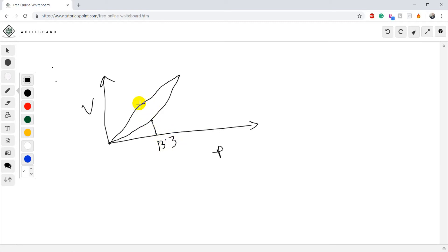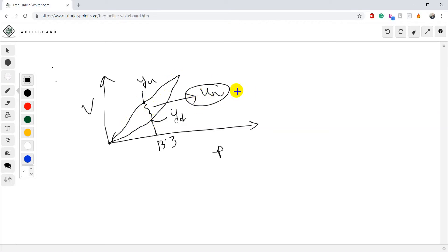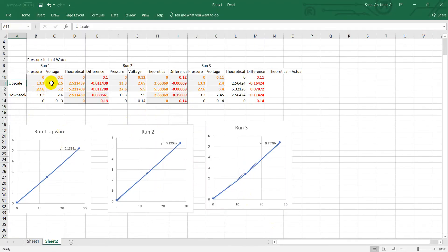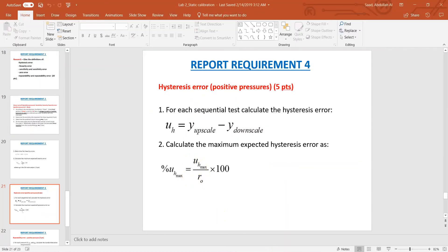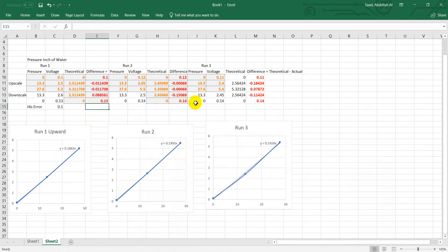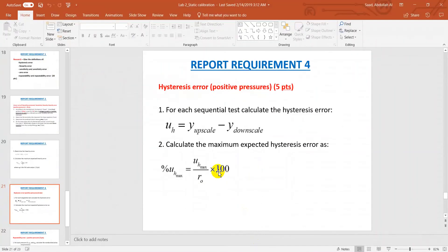You can see there is some hysteresis. At the midpoint — around 13.3 or wherever it is — going up gives one value and coming down gives another. This is y-upscale and this is y-downscale. You calculate the difference between these values. The function is simply one minus the other, and this gives the hysteresis error. You repeat this for every point and find the maximum hysteresis error among the three runs.